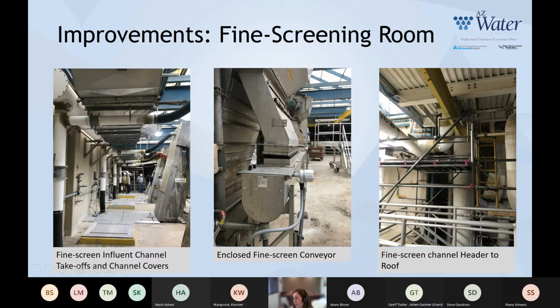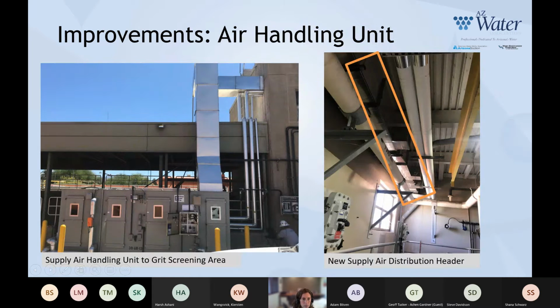And then you can see we built, it's really hard to see, but you can see this duct, which is the new channel header from the fine screen influent channel and screens, with a new penetration up through the roof so that it could branch into the main duct on the roof without being limited by any suction draw. The new supply air handling unit was located on the west side of the fine screen truck loadout bay ramp. And that supply air duct went up and into the building on the north end. It was a really tight squeeze, but we were able to fit it in right there on the west wall, just above the window, to provide some fresh air to that side of the building.